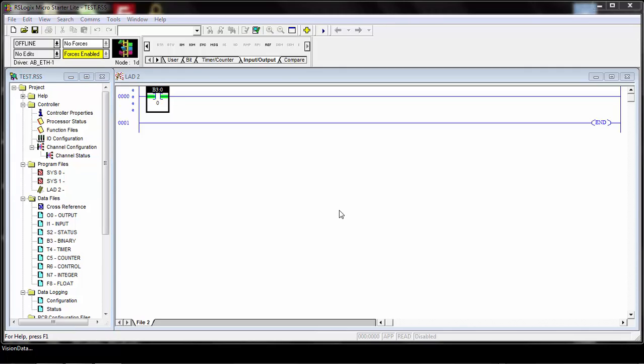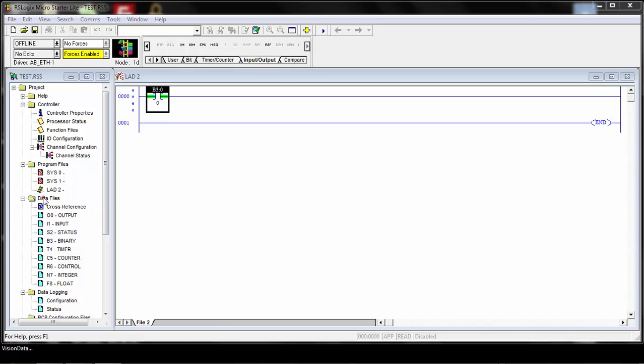Since the MicroLogix type PLC does not do the implicit fixed cycle communication, like on the ControlLogix and CompactLogix, we need to set up the explicit message command. In order to do that, we need to add some data files to the PLC program so we can send our data back and forth and create that message.